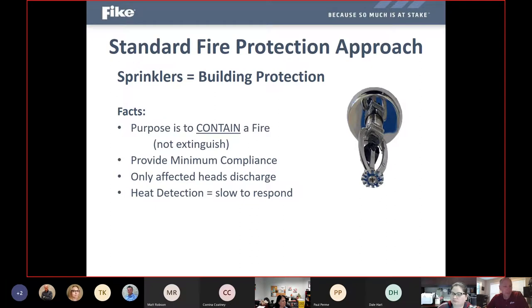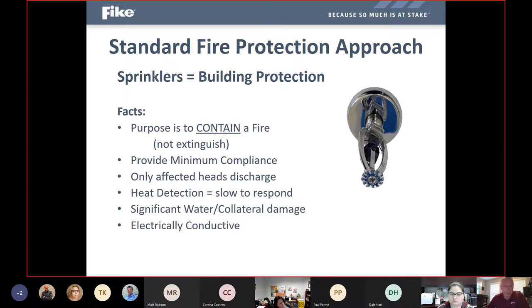But the only time the head is actually going to start to discharge water is when the thermal increase below it is significant enough to melt off the head and allow that pathway to open. And we're talking about significant water discharging from a head when it goes off. So you're going to have significant water and collateral damage to deal with after an activation. And obviously water is electrically conductive. So anytime you have a sprinkler head go off, there is going to be expected a significant business interruption.